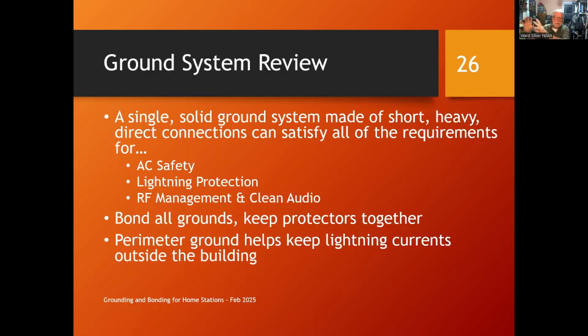You can have one in some kind of switching rack outside the house, and you can have another one inside your station. Keep all of your protectors together. So wherever that surge goes, they all fire at the same time, and everything goes up and down together. All of your ground electrodes shall be bonded together outside the house.